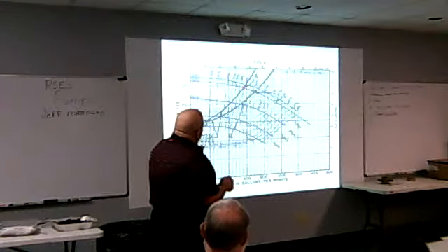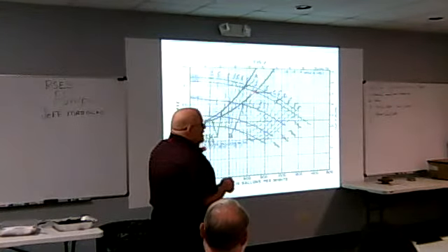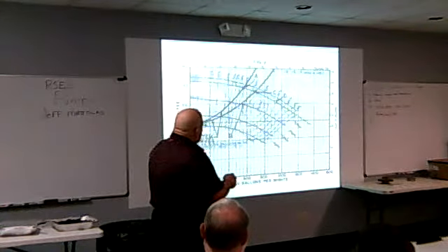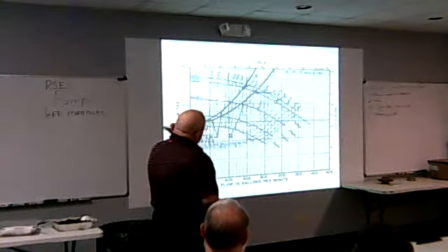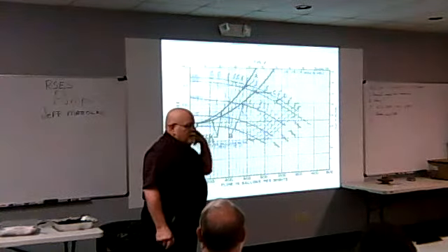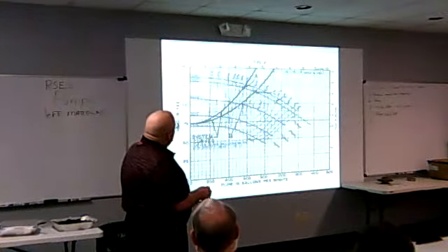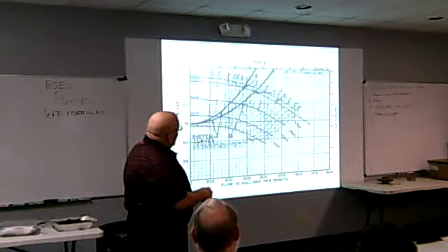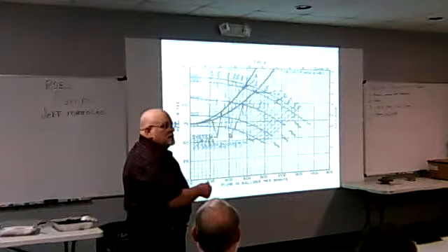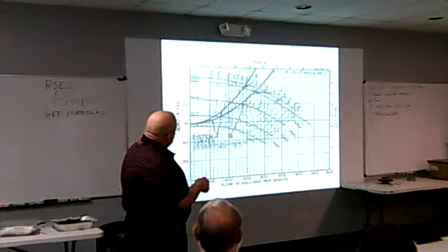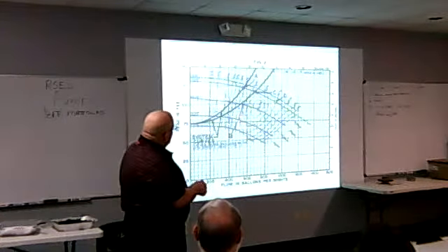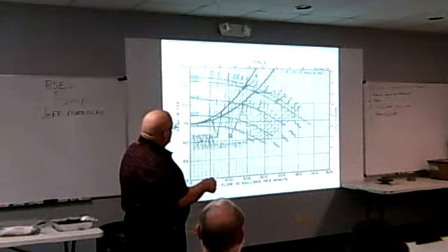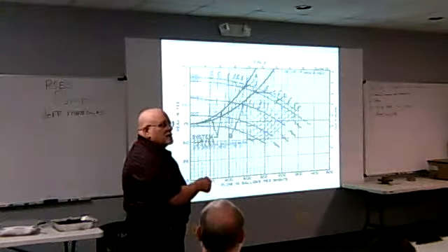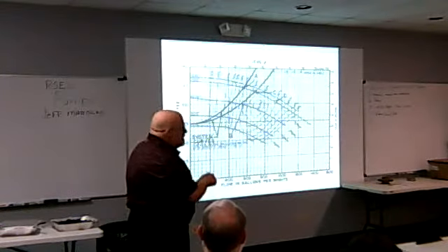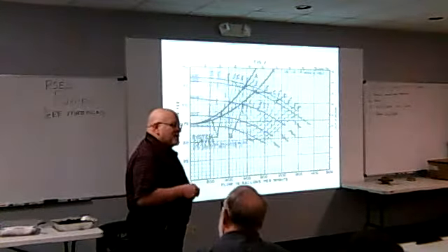They gave us this impeller, but in reality, this is what we had. For the flow we need, we have to be way here, since we could trim that impeller, but we're going to operate here. And when they talk about non-overloading throughout the curve, you hear this all the time. See, this is 30 horse here. If I go out my whole impeller curve, I have to use a 40 horse here per se, just by this curve. Because if I let this pump go, if my design's off, let's say my design's way off, my curve's here, I can get out here in the curve and overload. But if I plot my system curve, I can avoid that.